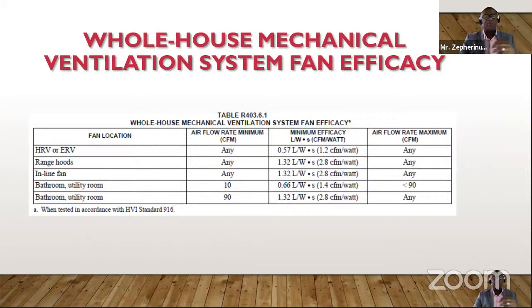So this table R4 3.6.1 would now provide you with the different locations, what the airflow rate, the minimum airflow rate should be, and as well the minimum efficacy in liters per watts per second, which is the SI units, and the imperial units would be CFM per watt. So you would use this as your guide to meet the requirements of the code when ventilating your residential building.